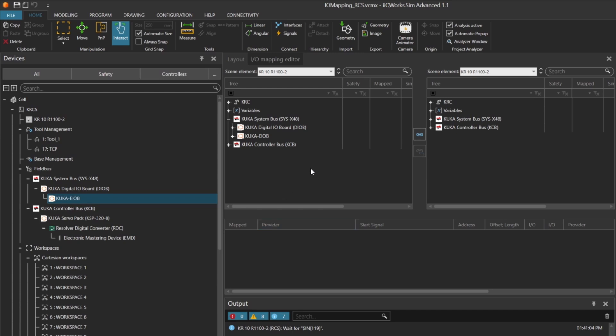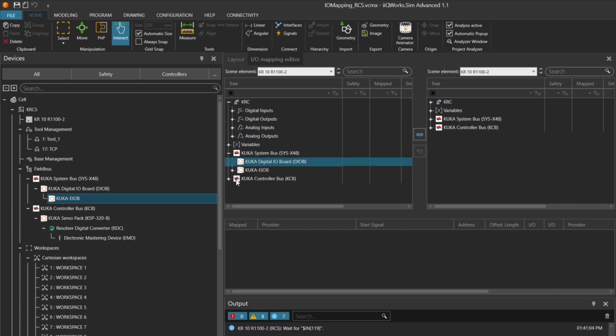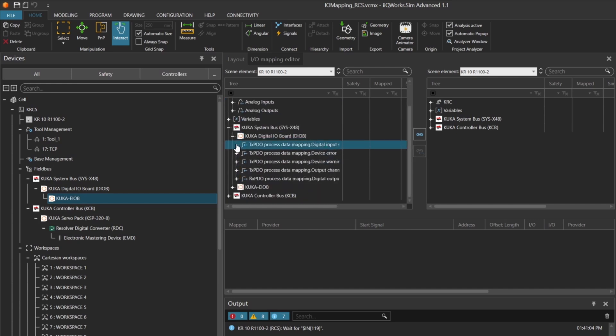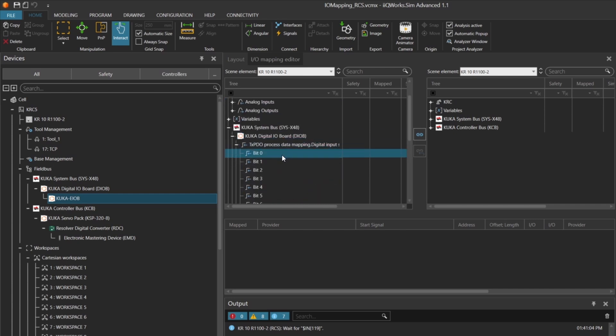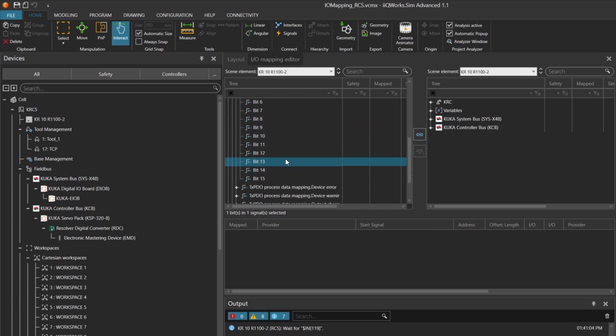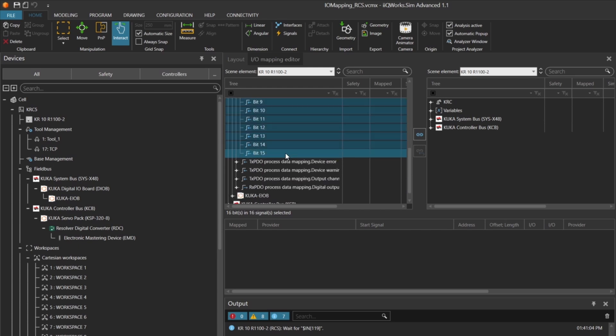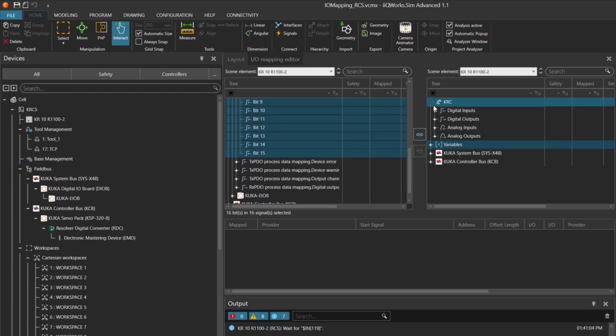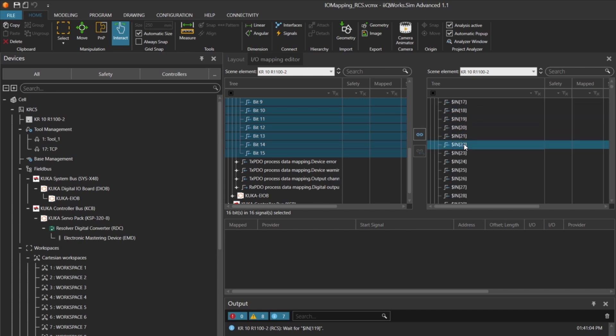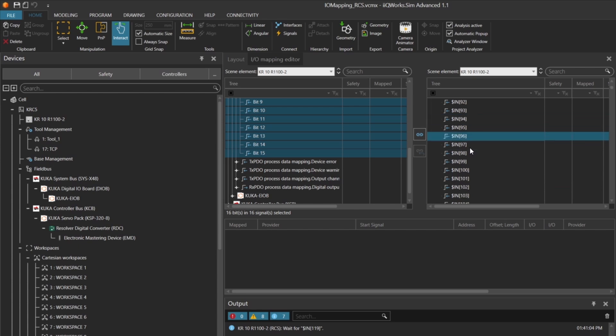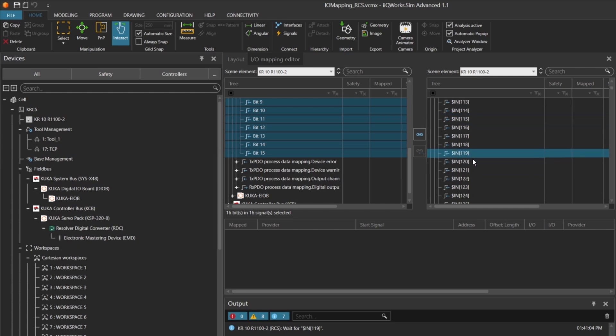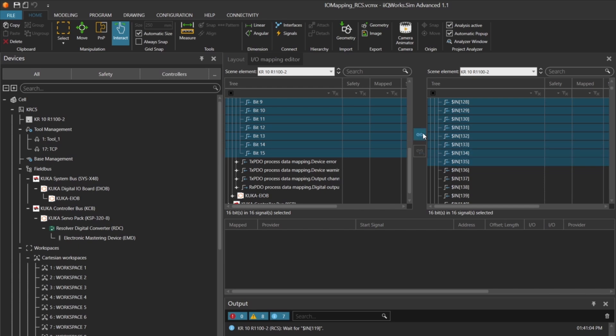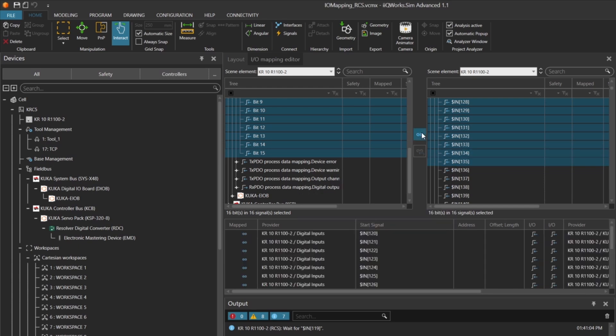On the input side, we need input 119 for the trigger signal and inputs 120 to 135 for the integer signal color num. Additionally, to transfer the gripper position signals to the VRC, we also need inputs 101 and 102. Let's start by selecting the digital inputs from the first module. We'll mark all 16 inputs and assign them to the robot. These inputs will be used for the color num signal, which controls which block the robot should handle.